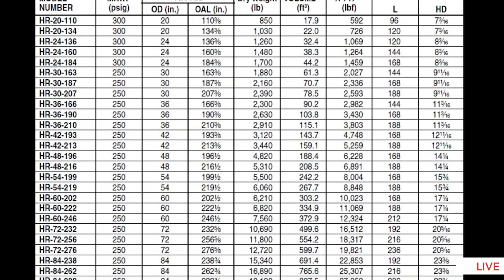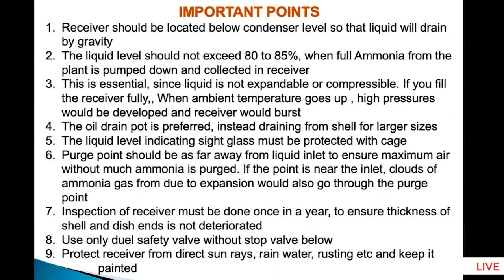These are the various sizes of receivers. How much is the weight of the receiver? What is the internal volume? How much ammonia quantity can it accommodate? Etc., etc. This chart will be available. HR20 110 means 20-inch diameter, 110 inches length, and these are the various sizes I've given up to 96 inches. You can select the receiver based on your quantity of ammonia, pounds of ammonia, which is 85% full on this vessel.